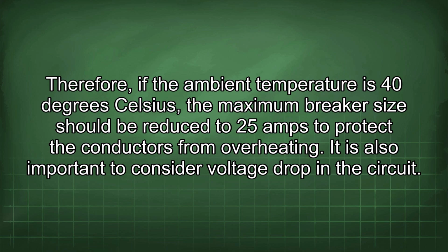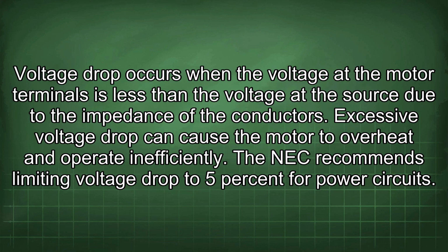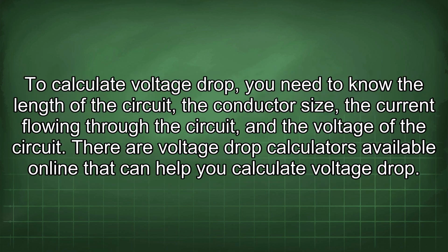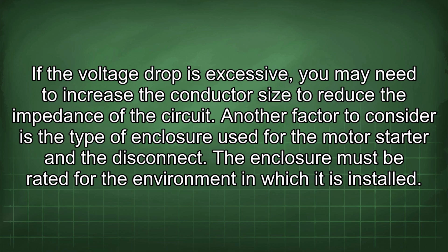It is also important to consider voltage drop in the circuit. Voltage drop occurs when the voltage at the motor terminals is less than the voltage at the source due to the impedance of the conductors. Excessive voltage drop can cause the motor to overheat and operate inefficiently. The NEC recommends limiting voltage drop to 5% for power circuits. To calculate voltage drop, you need to know the length of the circuit, the conductor size, the current flowing through the circuit, and the voltage of the circuit. There are voltage drop calculators available online that can help you calculate voltage drop.